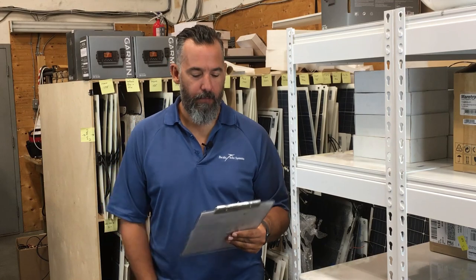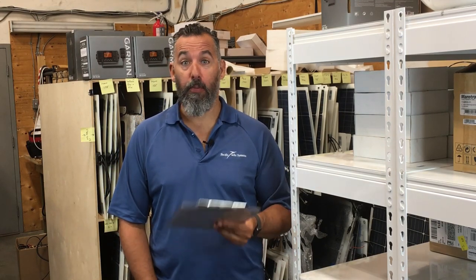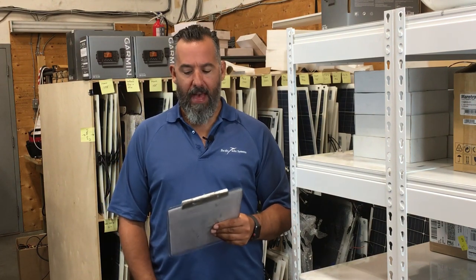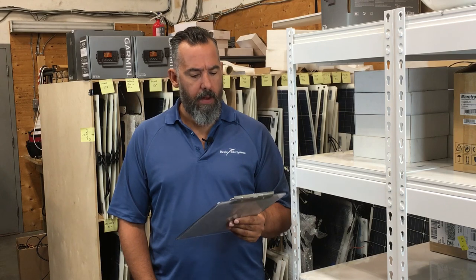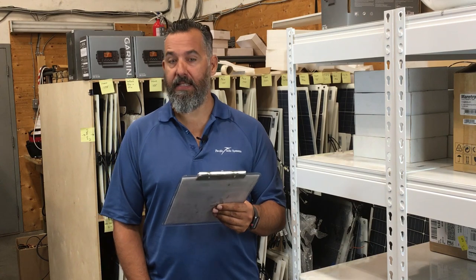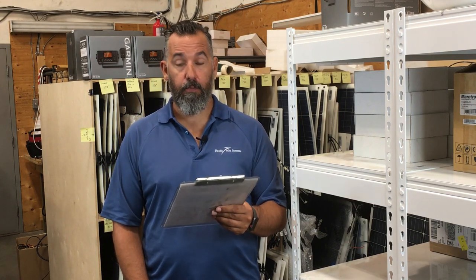Hi everyone, Jeff Cote here at the Pacific Yacht HQ. So we've got a fellow boater asking us a question. Brad asks: Jeff, you say fuse the alternator at the battery. If that fuse blows, won't it toast the alternator? I'm installing a Blue Sea Systems battery switch and an ACR. The alternator is 55 amps with an internal regulator.